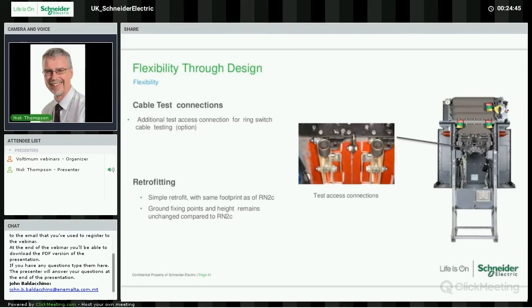Cable testing is something that you need during either commissioning or after you've got a fault on a cable, and it's a UK habit to have a separate cable test device, introduced way back in the early 90s and possibly earlier than that with RN2C and following on with RN2D. It's a drop-down star bar for your ring switches underneath, which then gives you access to the circuit. You can only drop the star bar down when you get circuit earth.